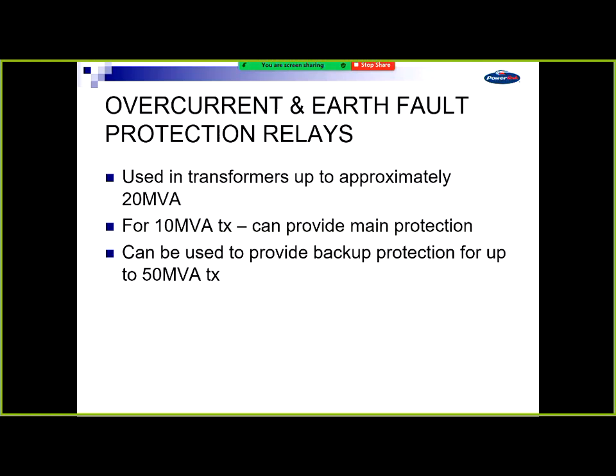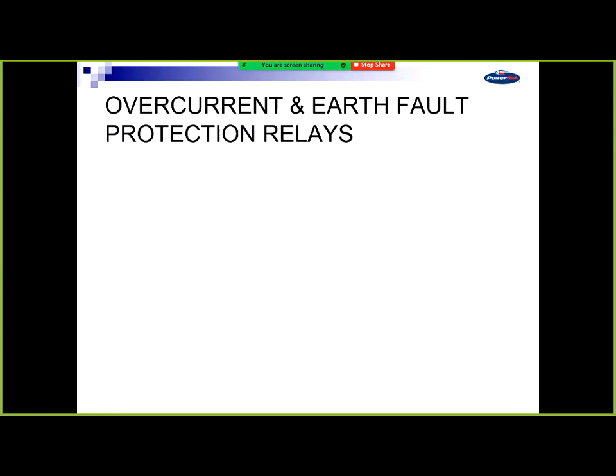A lot of their sites have a single bus zone protection. In our transformers, we have an overcurrent relay graded over top of their bus zone protection to trip if their bus zone fails. Bus zone relay failing is not very common. It's a lower voltage, so it can be a bit slow, and just an overcurrent is a backup. In that case, it is a backup, but for our network, it's X and Y. They're racing one another. There's not a backup style of protection. Common up to 66 kV and those ones.